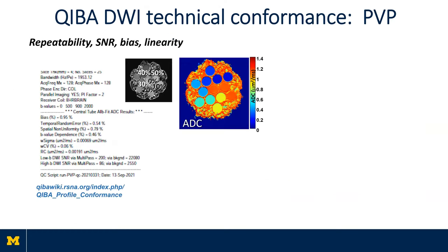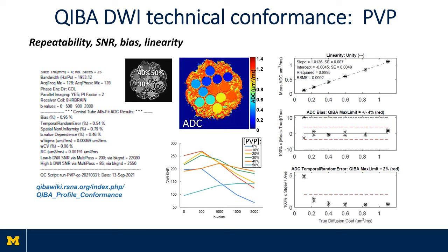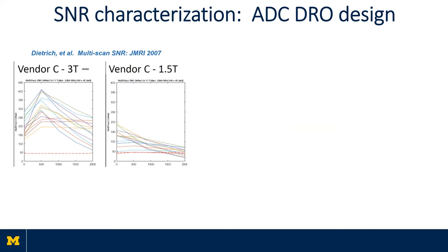The ice water component of the NIST PVP phantom is also used for conformance testing by the QIBA DWI profile. System performance metrics are evaluated for bias and B-value dependence, short-term repeatability, and signal-to-noise. System linearity is also measured over the order-of-magnitude ADC range provided by the phantom components, as shown here for an example QC report. The signal-to-noise measurement performed using a multi-scan procedure provides a good approximation of system noise by measuring it from temporal variability of the DWI signal as a function of B-value.